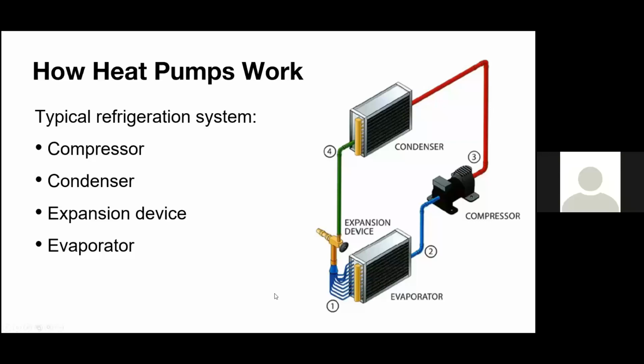So we also don't use air, we use refrigerant, as we like to control the mixture that's in there, the evaporation and condensing points. We want to make sure we don't have any different substances in there that will evaporate and condense at different temperatures. So again, we use refrigerants. And the other big difference is that a lot of the energy exchange comes in with the condensing and evaporating. So when we take that hot compressed refrigerant outside, we cool it to a point where it actually condenses into a liquid. This is why we call it a condenser outdoors.